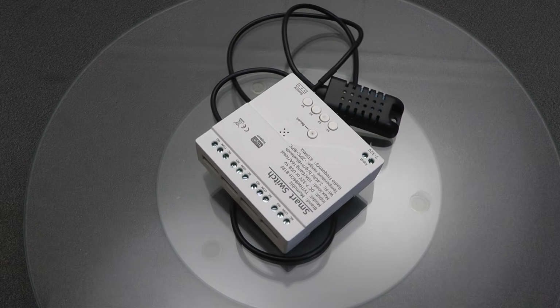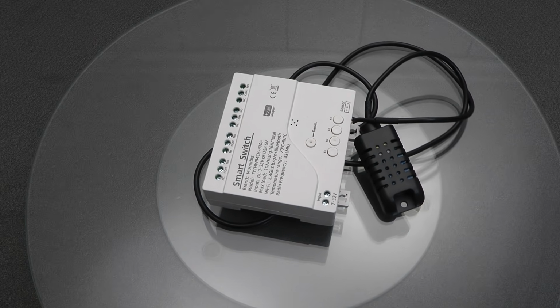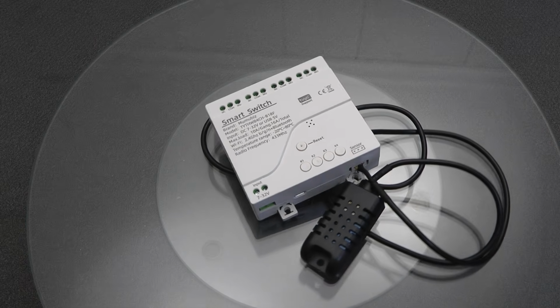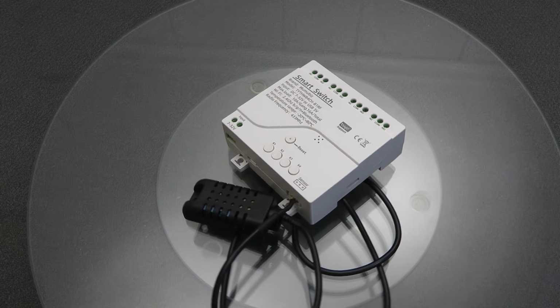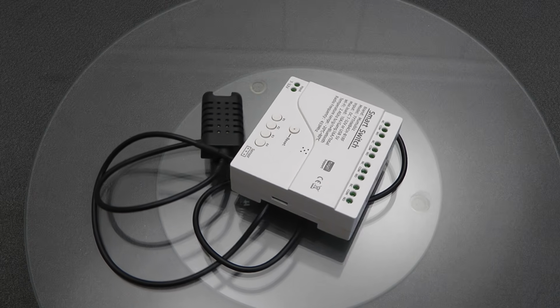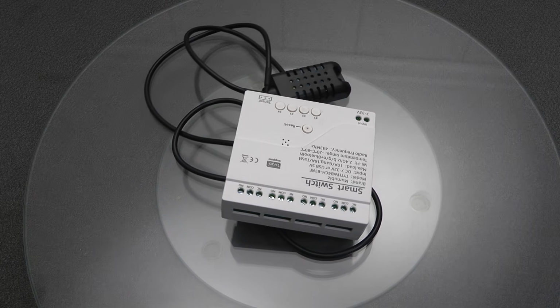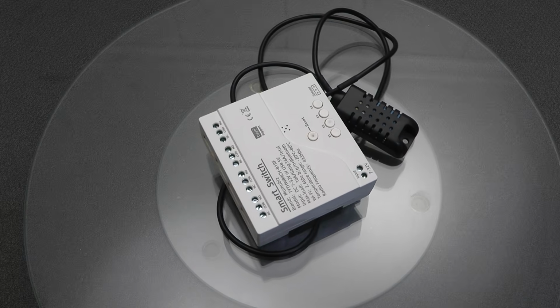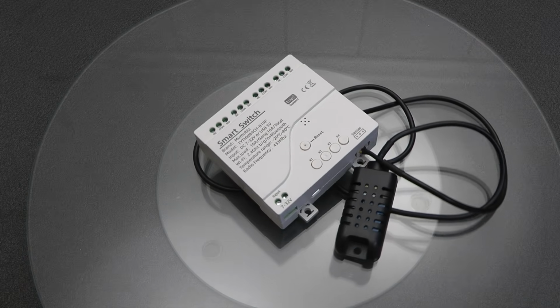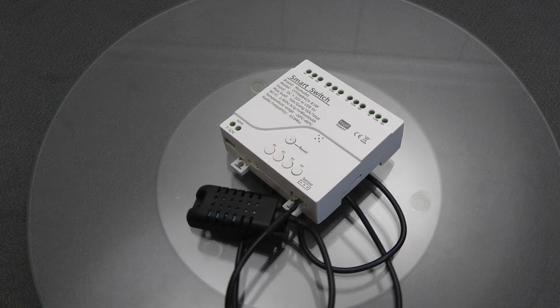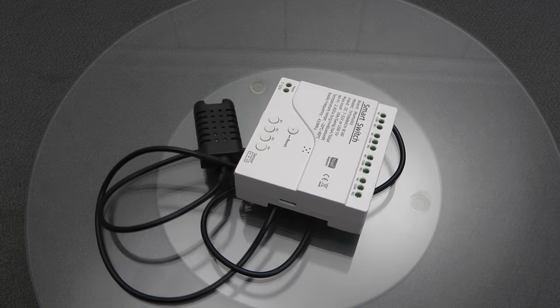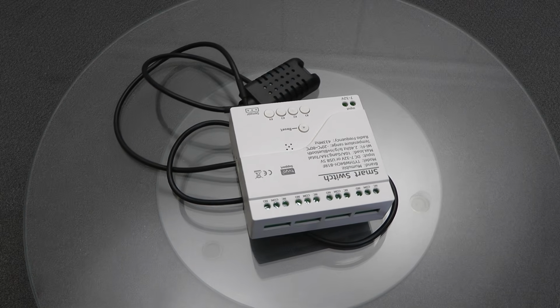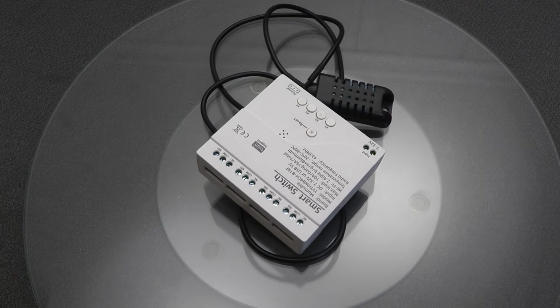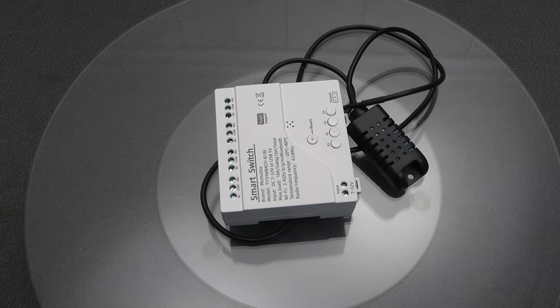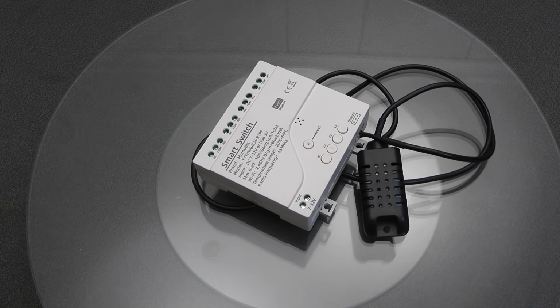The main difference of this version is support for an external temperature sensor or a temperature and humidity sensor. Temperature is displayed with an accuracy of 0.1 degrees and humidity with a step of 1%. The declared temperature measurement range is from -20 to 100 degrees and the humidity range is from 5 to 80%. For temperature, the manufacturer states an error of plus or minus 0.5 degrees, and for humidity, plus or minus 5% in the range from 20 to 80% humidity.